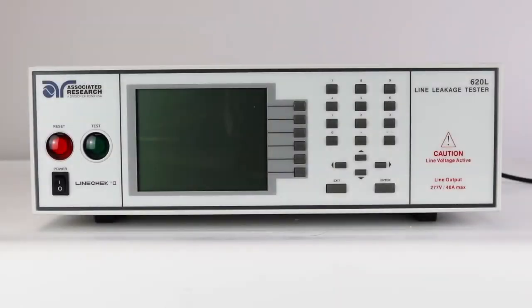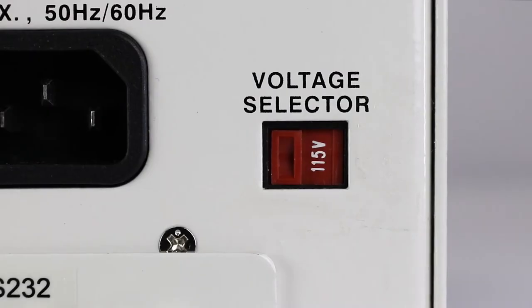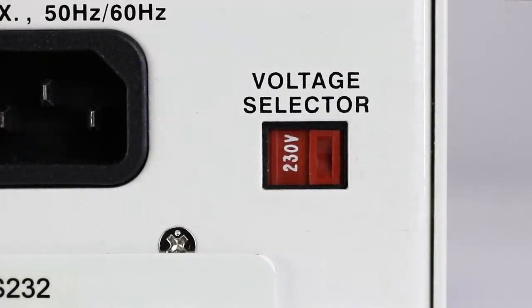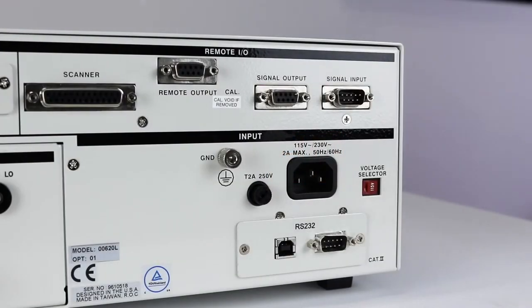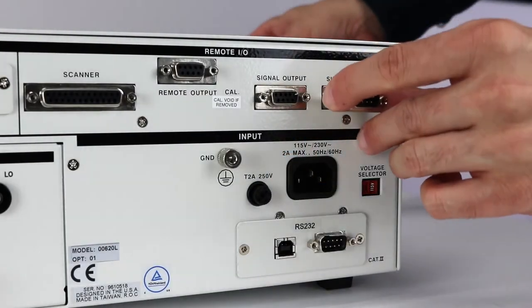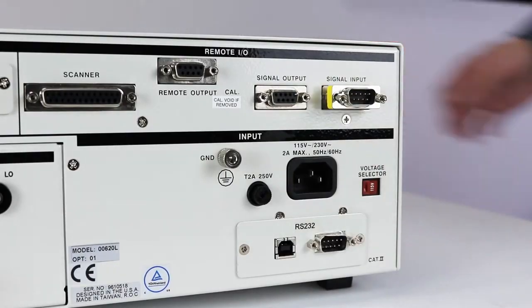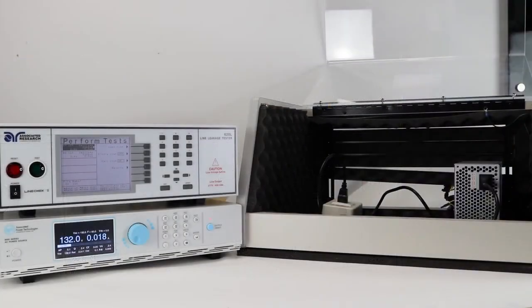First, you'll need to power up the LINECHEK instrument. Check to be sure the correct input line voltage has been selected on the rear panel, either 115 volts AC or 230 volts AC. You'll also need to insert the remote interlock key into the signal input terminal on the rear panel. The instrument will not output voltage unless you use this key. This allows the user to wire the instrument to the doors of the DUT enclosure. This is a safe workstation best practice.